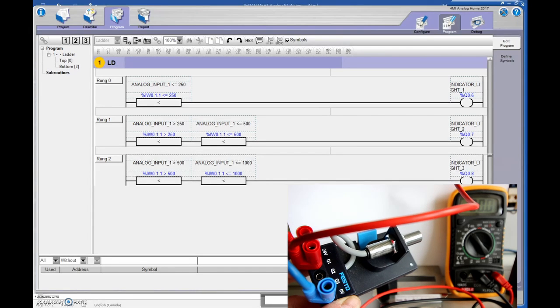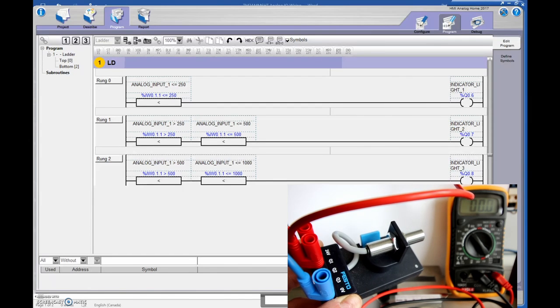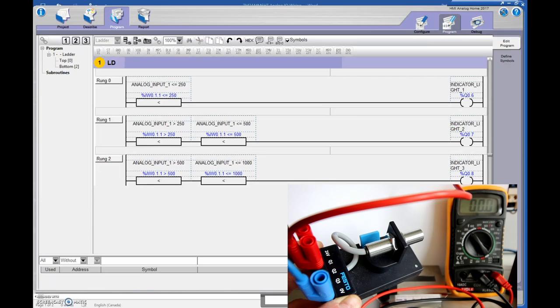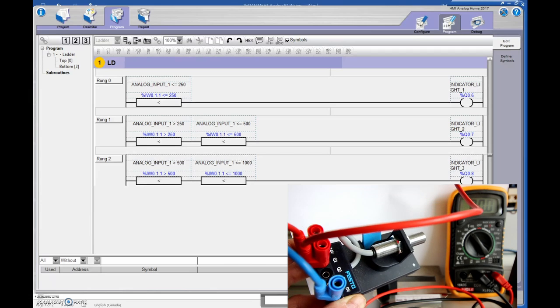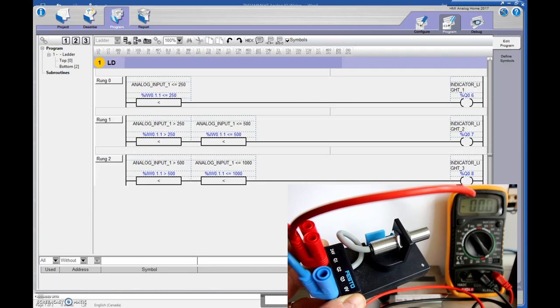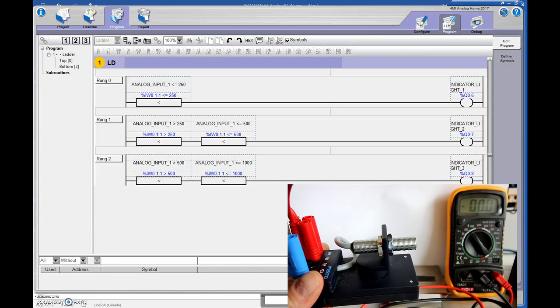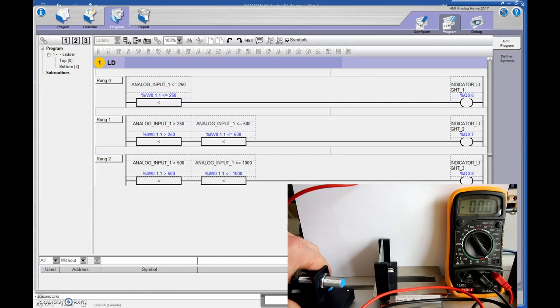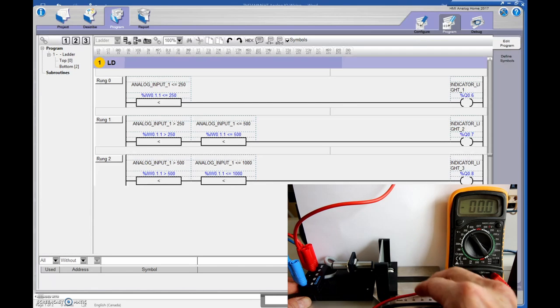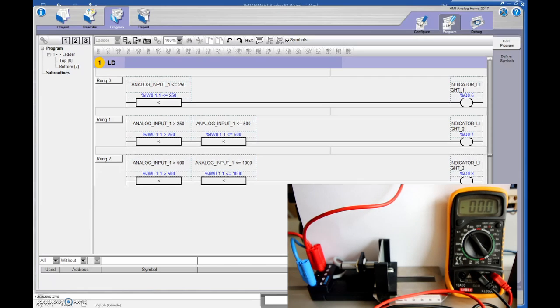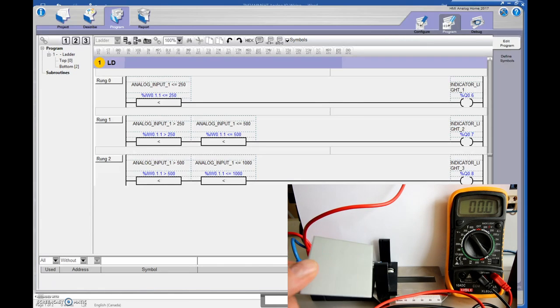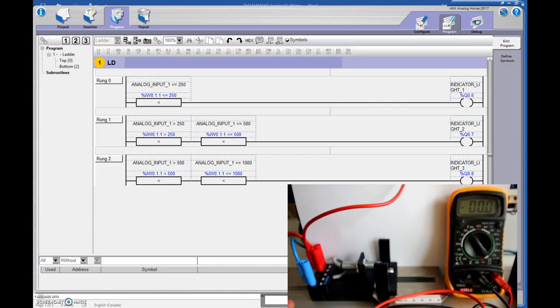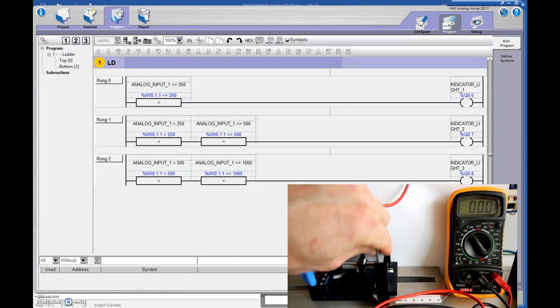So let me start off with this sensor here. So I have an analog sensor. This is a three-wire sensor. And this guy is able to punch out 0 to 10 volts or 4 to 20 milliamps, depending on which output I'm using. Right now, I've supplied it with 24 volts. And I'm taking the signal off of Q1. And Q1 provides me with a 0 to 10 volt signal. And the maximum sensing range on this guy is about 6 or 7 mils. So what I'm going to do is I'm going to place that right here on my aluminum channel. And then I'm going to butt that right up against my piece of metal there. So right there I just have a piece of galvanized steel similar to the ones that you've seen in the previous videos.